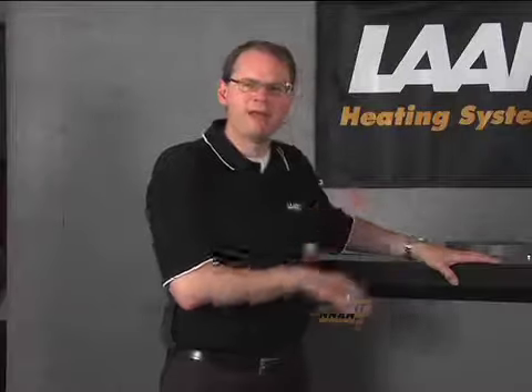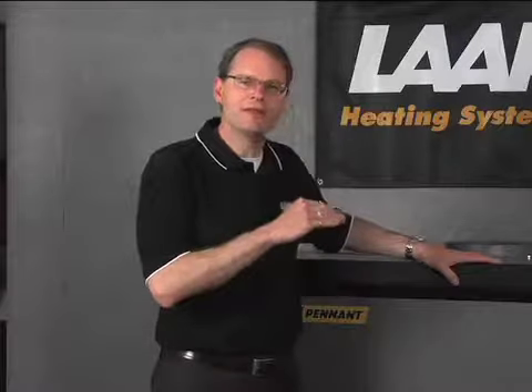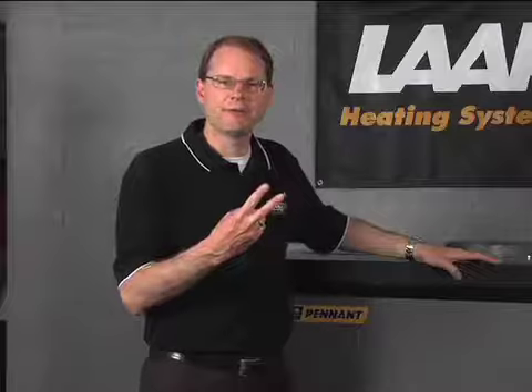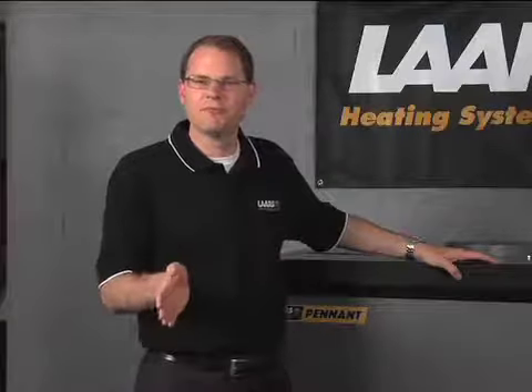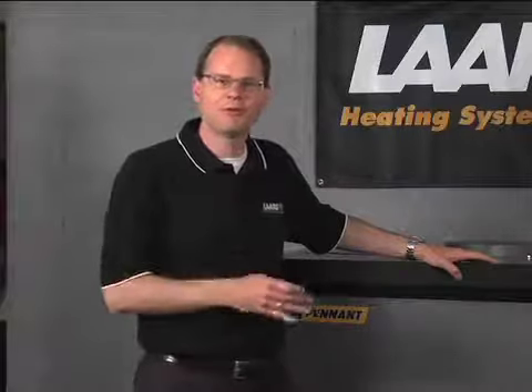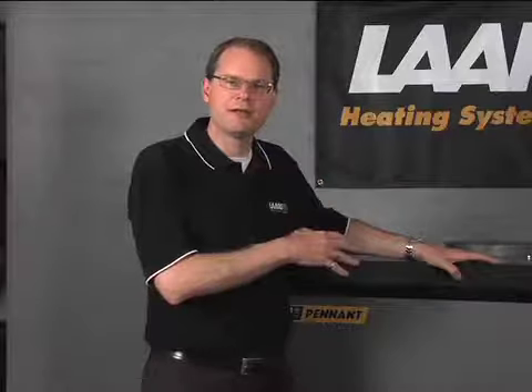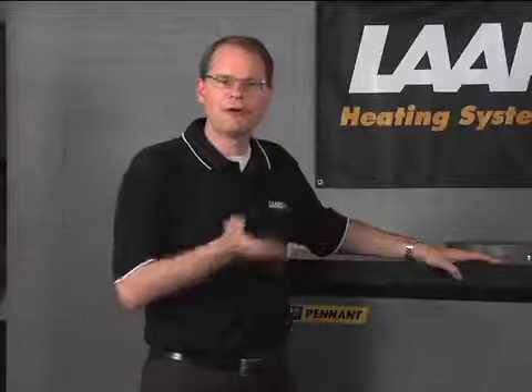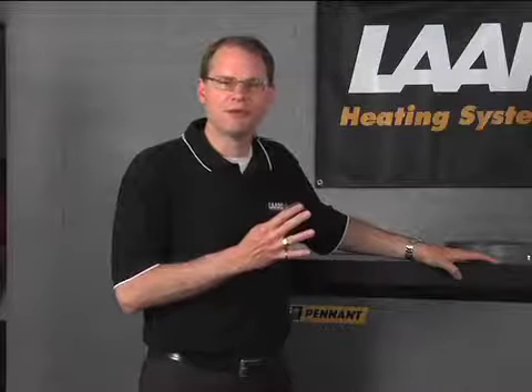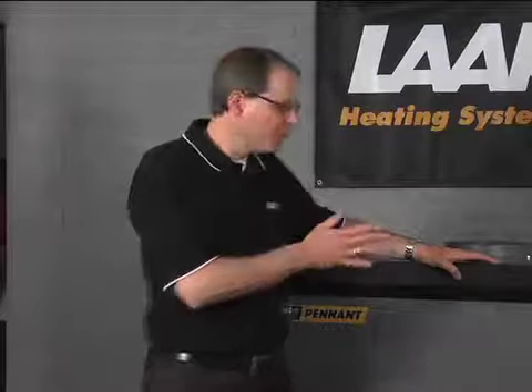The boiler is stage fired. So starting at the smallest size, which is 199,000 BTU input, up to 750,000 BTU input, these boilers are two-stage fired. Again, just to be clear, stage fired is different from fully modulating. When you look at some of the other product knowledge videos that we have available, some of the products we talk about there are modulating. But these are stage fired all the way up to the largest Pennant, which is 2 million BTU input. Those larger boilers are 4 stages of input. So if you have a mechanical room where you have 2 or more boilers, you've got a great opportunity to do some load partitioning on those boilers.